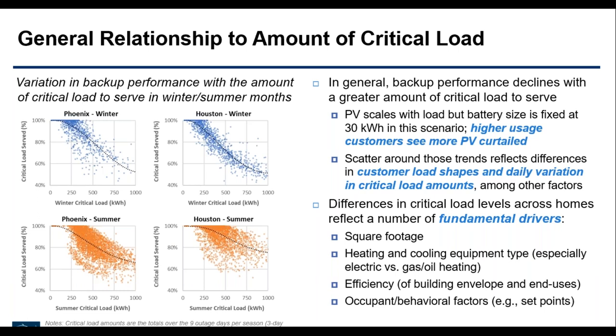As more load is present on a given place, the ability of that particular storage unit to serve the load becomes lower. The scatter around these trends reflects differences in customer load shapes and daily variation in critical load amounts. The black line represents the median values, reflecting in part the variation for a given critical load level based on behavioral aspects.